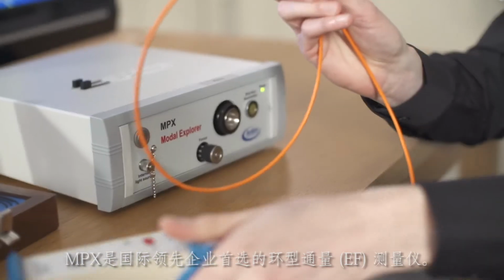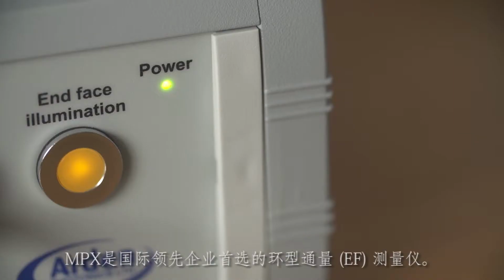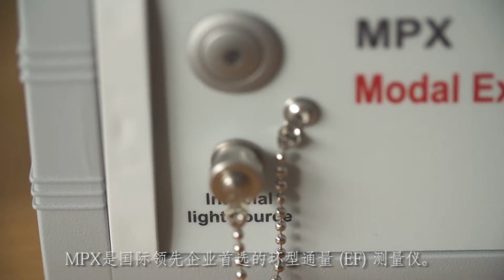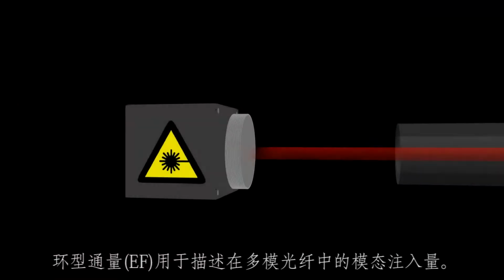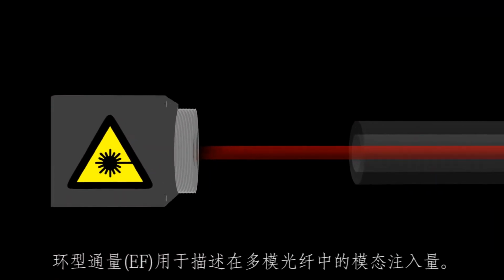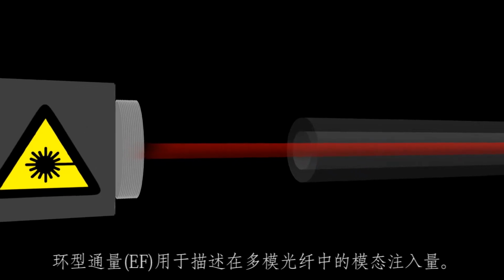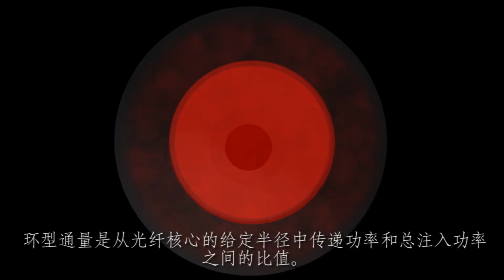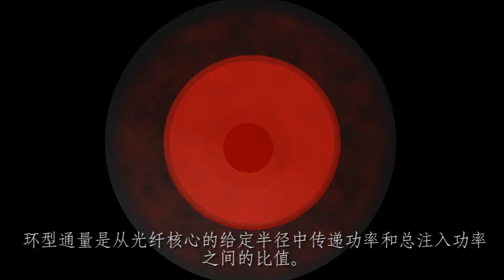The MPX Modal Explorer is the encircled flux meter of choice for leading companies around the world. Encircled flux is a measurement used to describe the amount of modal filling in a multi-mode optical fiber.